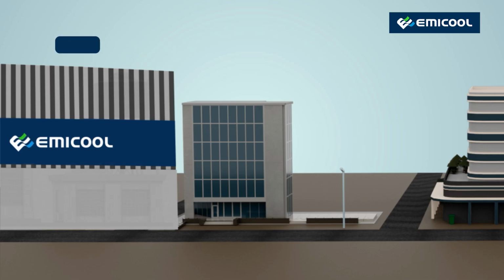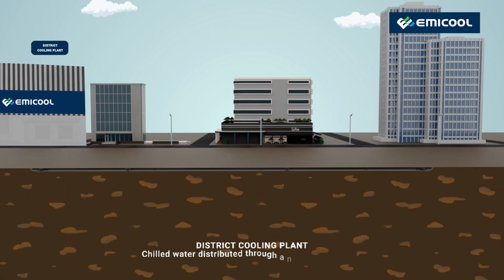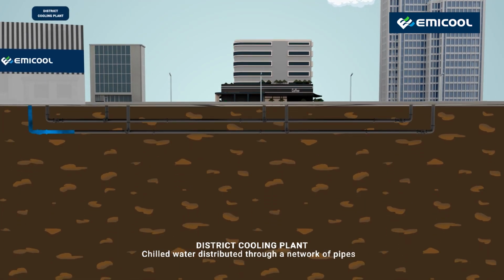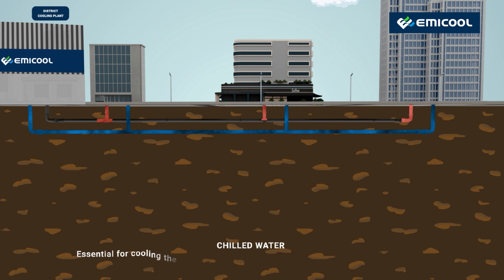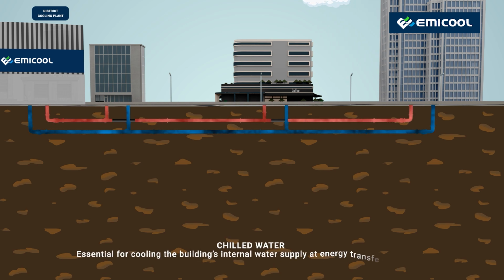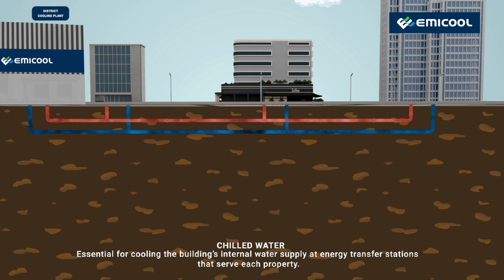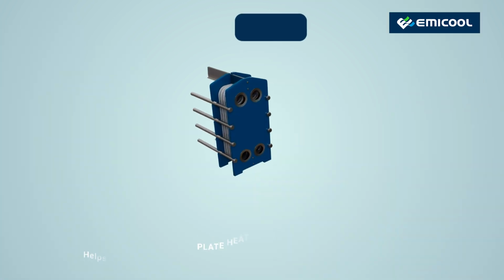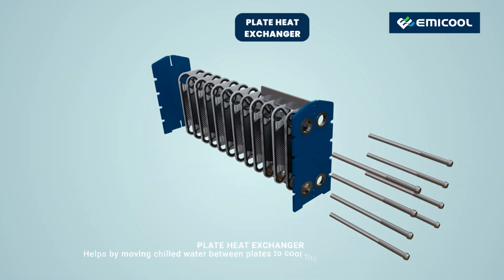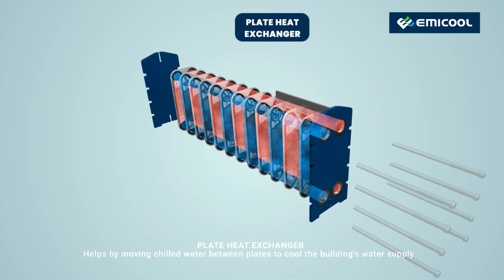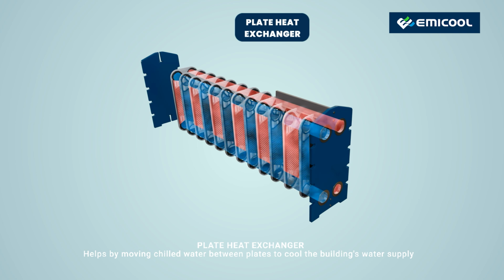This process begins at the district cooling plant, where water is chilled, then distributed through a network of pipes. This chilled water is essential for cooling the building's internal water supply at energy transfer stations that serve each property. A plate heat exchanger helps by moving chilled water between plates to cool the building's water supply.